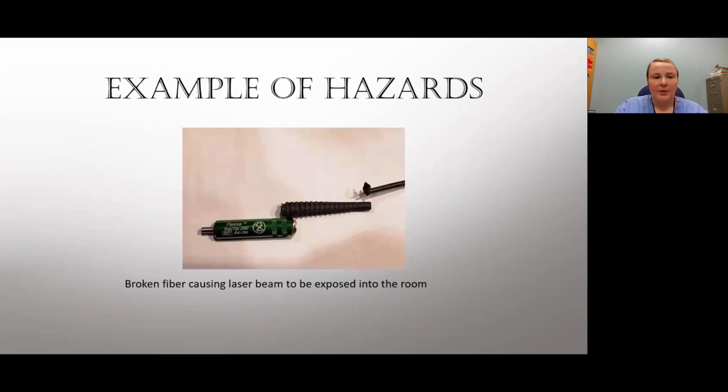So here's an example of a broken fiber causing the laser beam to be exposed into the room. What happened in this situation is the tip of the probe got really warm, so all the energy was going towards that part of the probe where it goes into the device. It's a hazard because the laser energy could be out into the room and not technically at the patient.